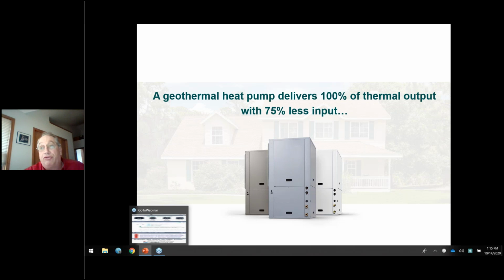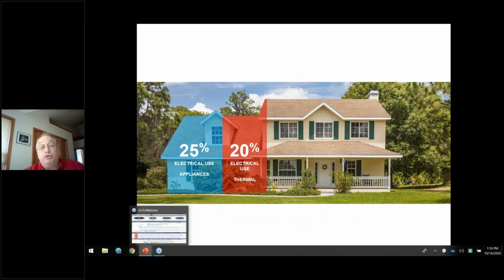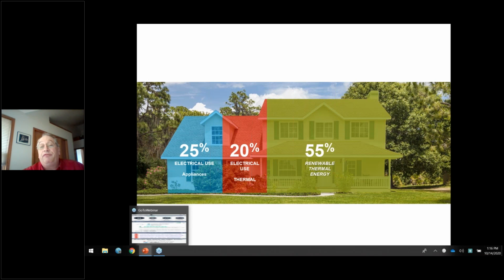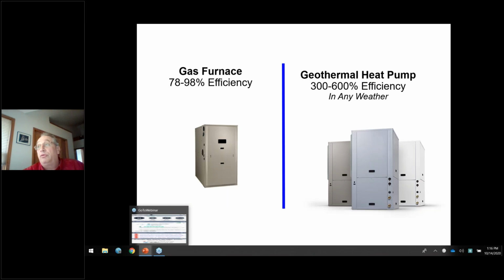And if we can go to electric, where geothermal heat pumps take that 100% of electric, we produce 100% thermal output with 75% less input. So we add just a little bit more electric use, but we gain 55% renewable energy for the thermal part of the home. Where a gas furnace is only going to give you 78 to 80% efficiency, and the rest would be going up your chimney and producing carbon monoxide. Where a geothermal heat pump, in any weather, any climate, is going to continue to present 300 to 600% efficiency.